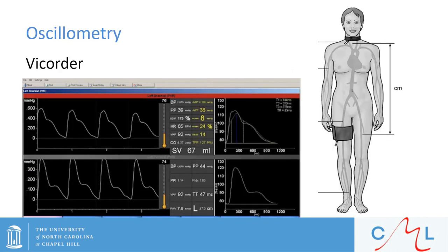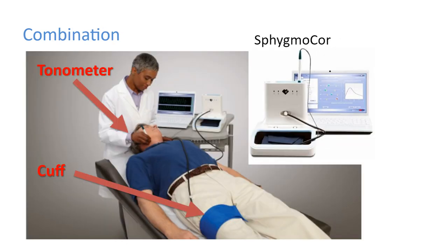With oscillometry, we use cuffs — simply blood pressure cuffs — to detect pressure waves. Here is an example setup for the Vicorder, which is an oscillometric device. Here we also see another device by AtCor called the Xcel, which combines tonometry — the pen-like pressure sensor — as well as the oscillometric component, which is the cuff placed around the thigh. We can also use ultrasound to assess pulse wave velocity, measuring the velocity waveform at proximal and distal sites, gating it to the ECG to determine the transit time.